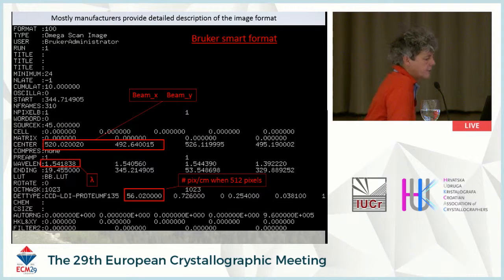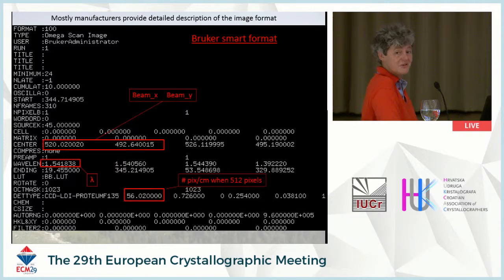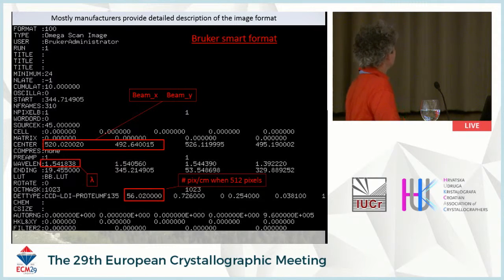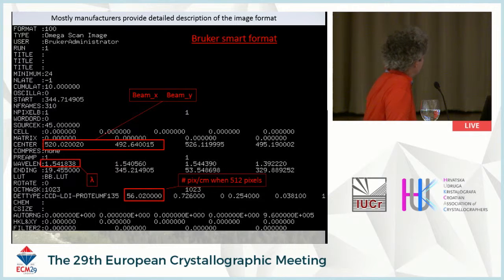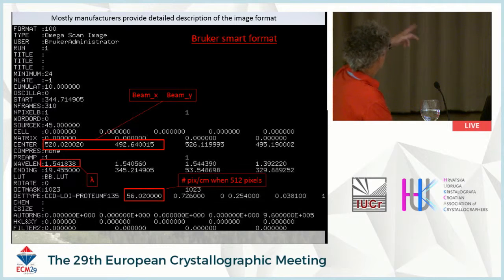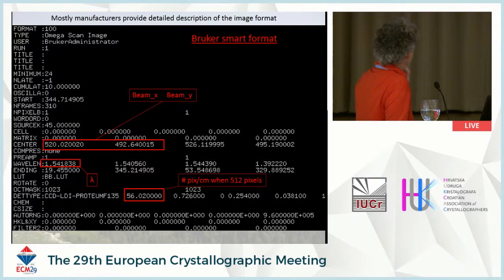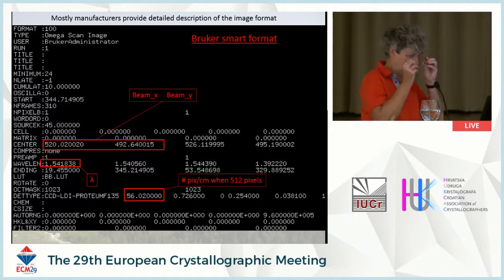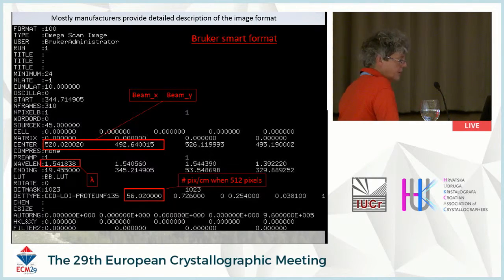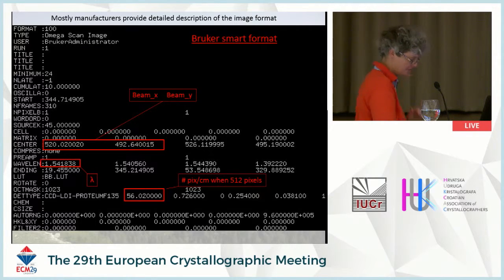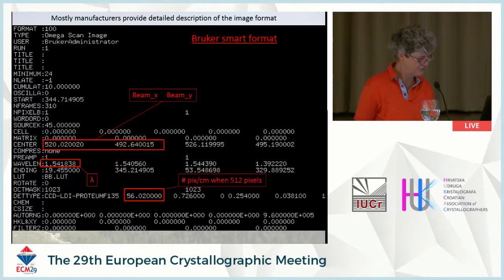The Bruker format is rather well documented. It includes beam x-y positions in pixels, the wavelength, and the pixel size — though the pixel size has to be inferred from the number of pixels per centimetre, so it's not straightforward. There are four goniometer angles: the swing axis of the detector (2-theta), omega, phi, and kappa.